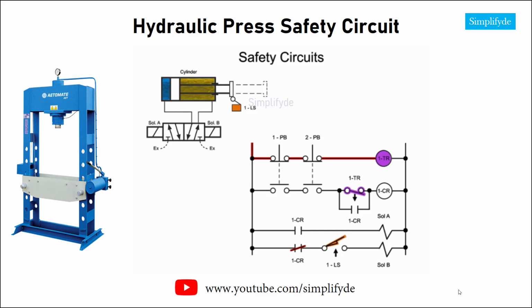If an operator depresses a single push button, power to the timing relay is removed and the off-delay timer starts to time. Only when an operator depresses both buttons within the off-delay timer countdown period can power flow to the 1CR control relay and energize the bypass circuit. The timing relay will remain closed until its countdown completes, usually just a fraction of a second. After the allotted time, the normally closed timed-open timer contact swings open. With the control relay energized, power flows to solenoid A.